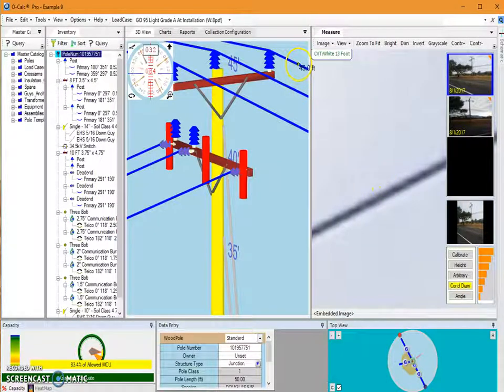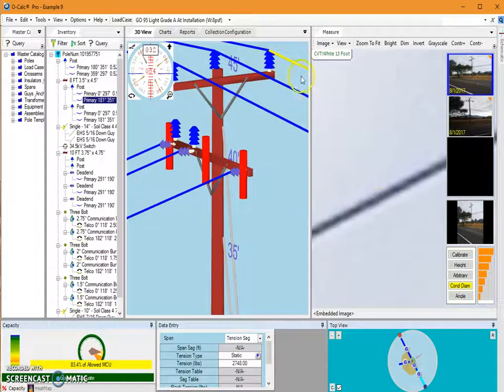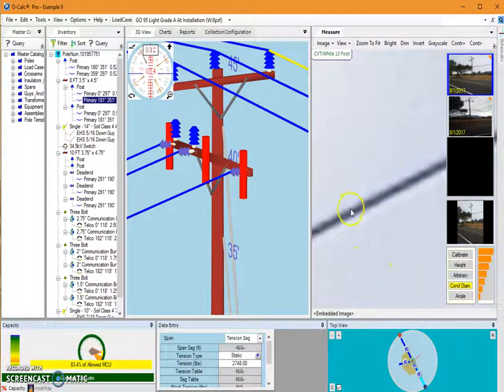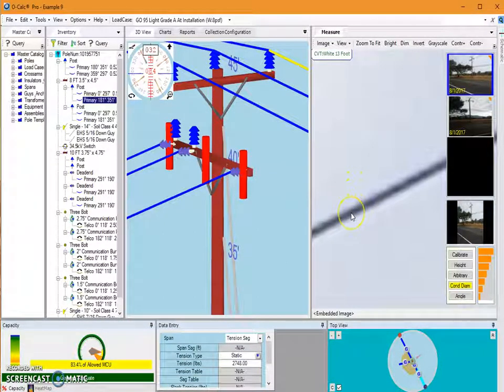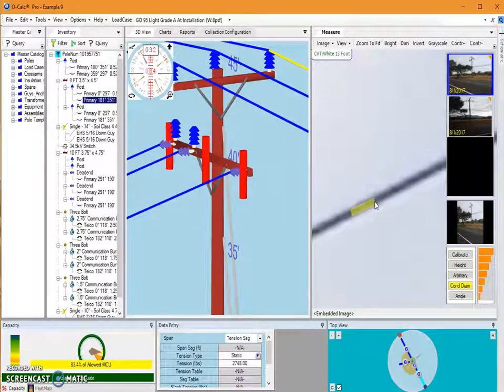This corresponds to a particular span in my 3D view. I'm going to select that span and choose the Conductor Diameter tool. What this tool does is, when you left click and drag, it creates an expanding yellow box — that's how it does the diameter measurement. I'm going to line up my cursor in the middle of that span so the point of my arrow is right in the middle, then left click and drag that box until it's about the same width as that span, and release my mouse click.